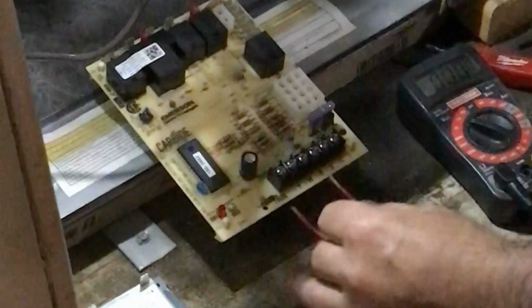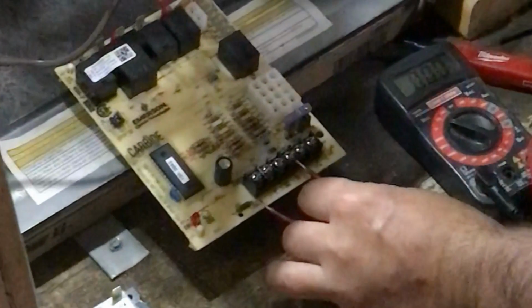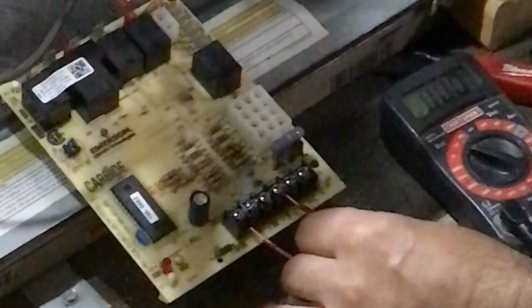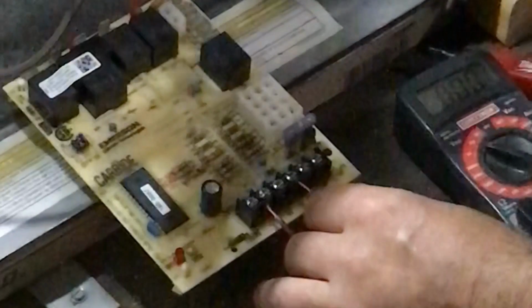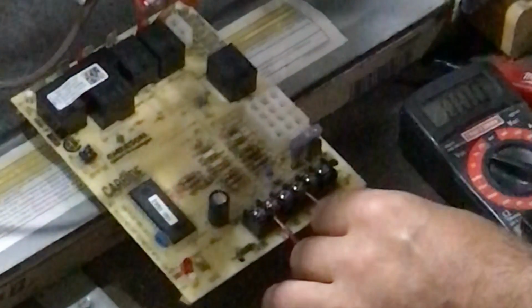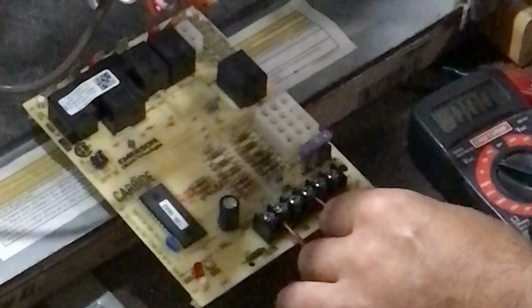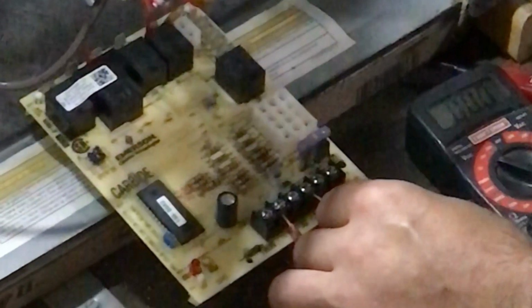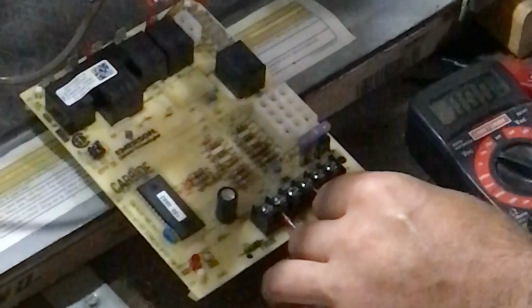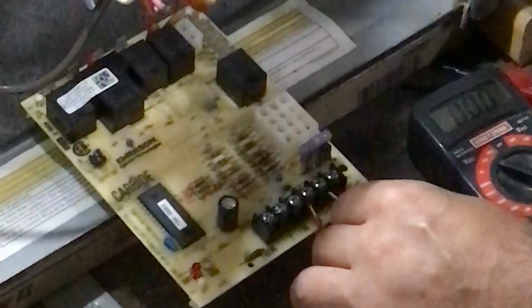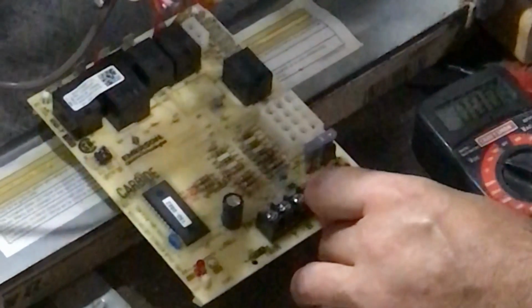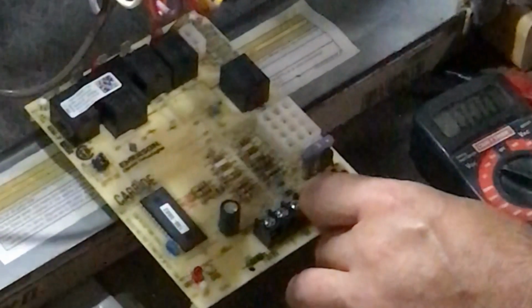So to test your contactor, you would go red, which is your power supply, to yellow. And if you go outside and your contactor closes and you got 24 volts to it, you know your thermostat's bad. Same thing with your fan operation. Red to green, your fan comes on, the thermostat's bad.